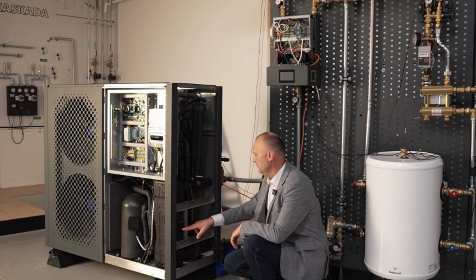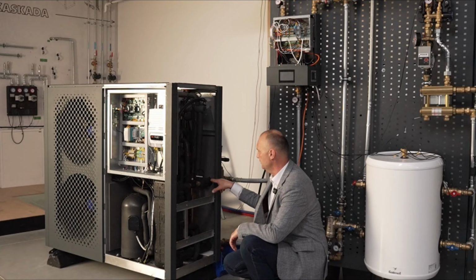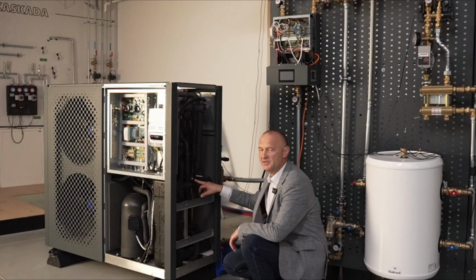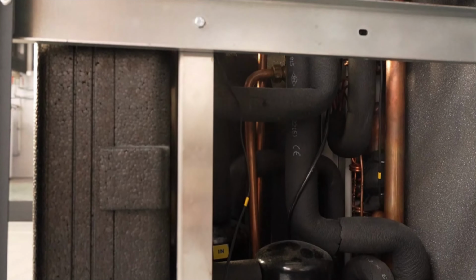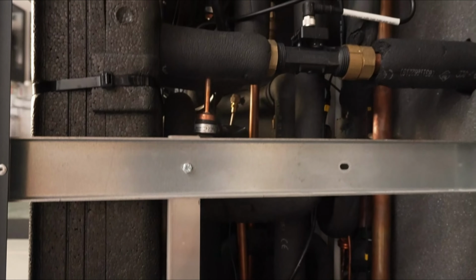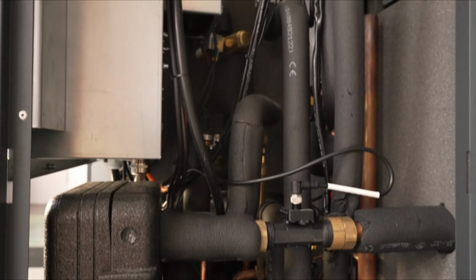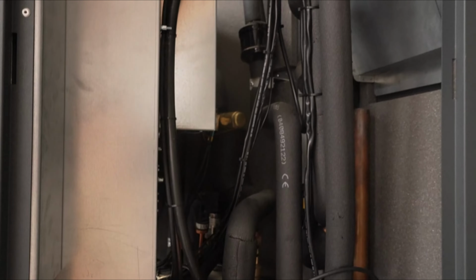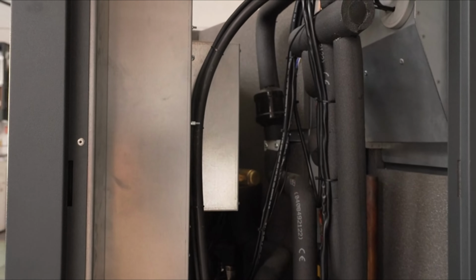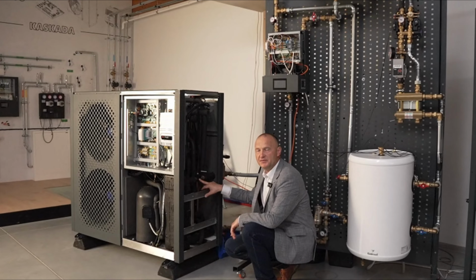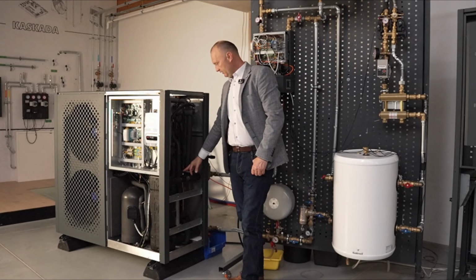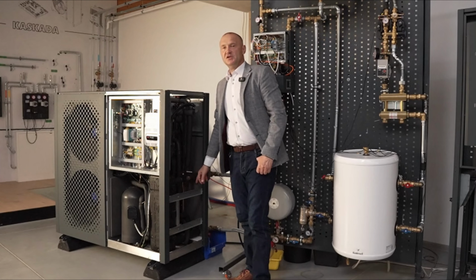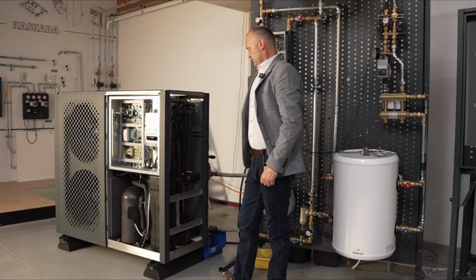Down here we have the water inlet from the system, which passes through the heat exchanger, and then the water outlet back to the system. A flow meter is also installed on this water circuit. This is a device that continuously monitors the flow of the heating medium, which is water at this moment, through the heat exchanger. Firstly, so that we have information on what this flow is, allowing the pump to adjust its operating parameters for efficient work and management, controlling the compressor. But also for safety, we need to have this information.